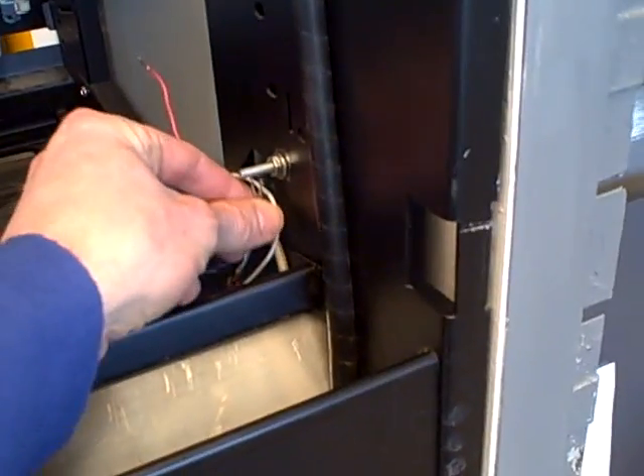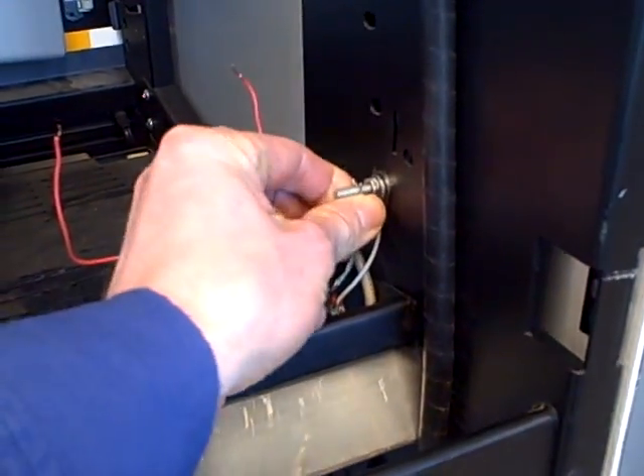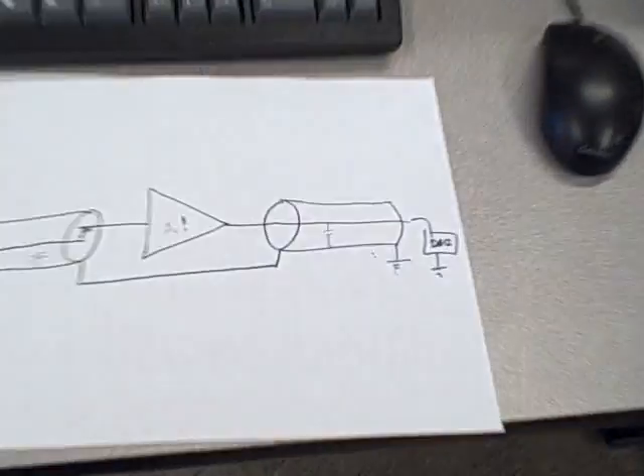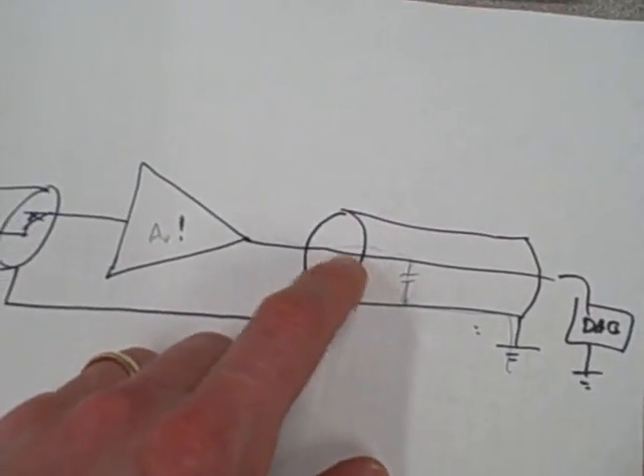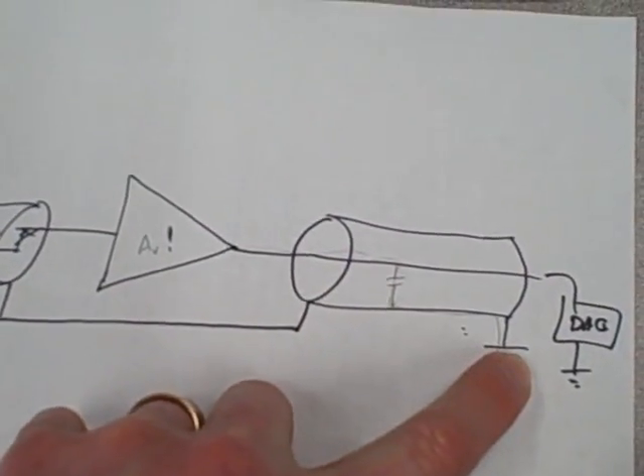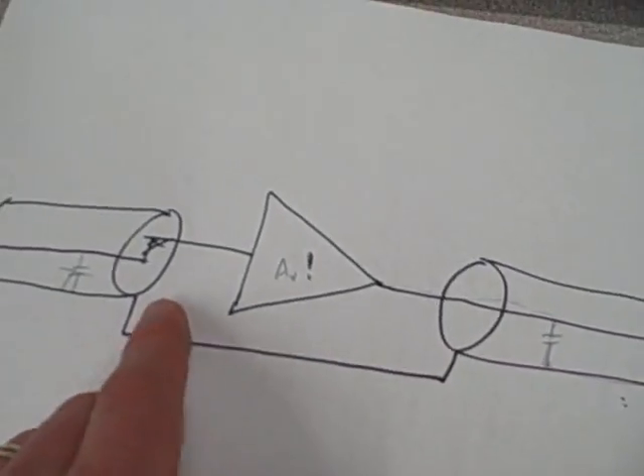On the other hand, if we connect our ground, we bond the shield wire to earth ground. What that does now is it provides a short circuit path for any capacitively coupled signal current to go straight to ground instead of being coupled over to the input wire. And as a result, our system works like it should. Now we have a voltage reading that's centered around 0 volts, and it's able to detect vibrations. As I hit the cabinet, you can see the vibrations being picked up.